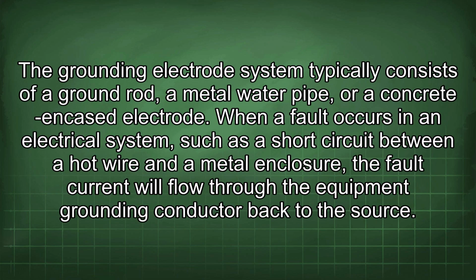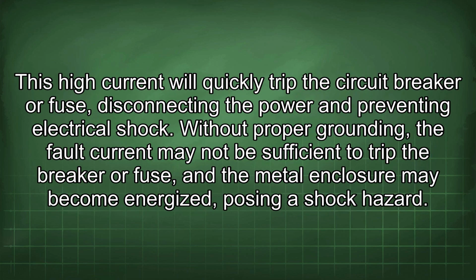The grounding electrode system typically consists of a ground rod, a metal water pipe, or a concrete encased electrode. When a fault occurs in an electrical system, such as a short circuit between a hot wire and a metal enclosure, the fault current will flow through the equipment grounding conductor back to the source. This high current will quickly trip the circuit breaker or fuse, disconnecting the power and preventing electrical shock.